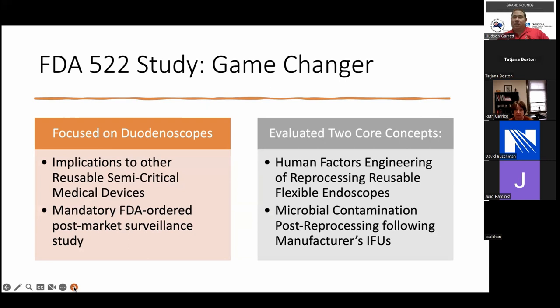Many of you probably have never heard of this because it's not something we see often. It is essentially a government-mandated study through the FDA for a regulated device. Essentially FDA says to the manufacturers, you must do this. Here's sort of the order, if you will, here's the timeline, here's the protocol, and here's what it needs to be done by. Failure to comply would result in immediate removal of those devices from the market. So FDA really had two different intentions with this. One was to say, how can we make sure that these devices are clean once they're appropriately reprocessed?